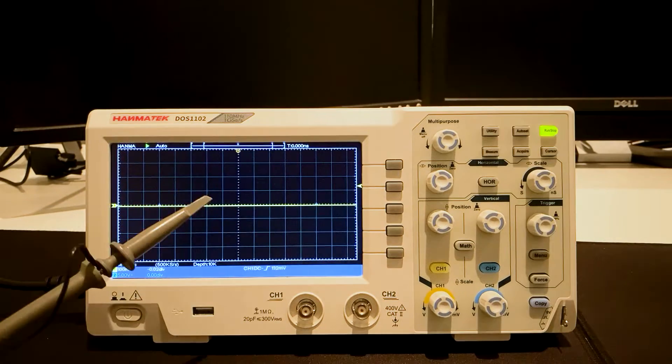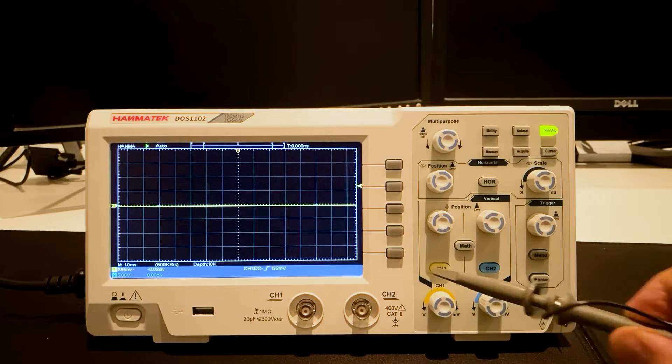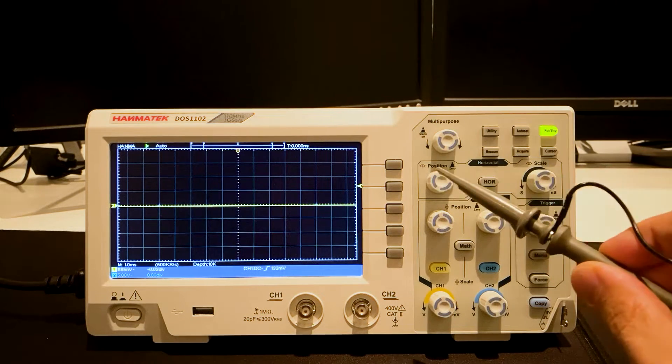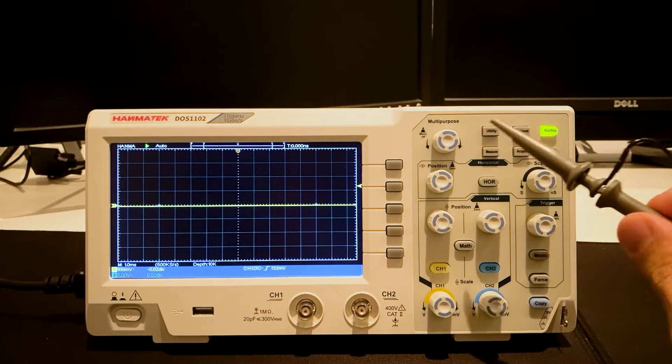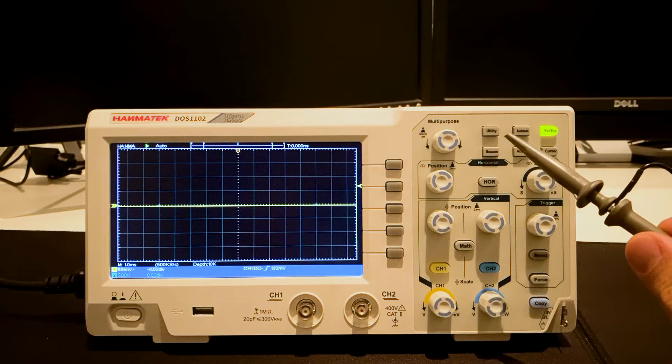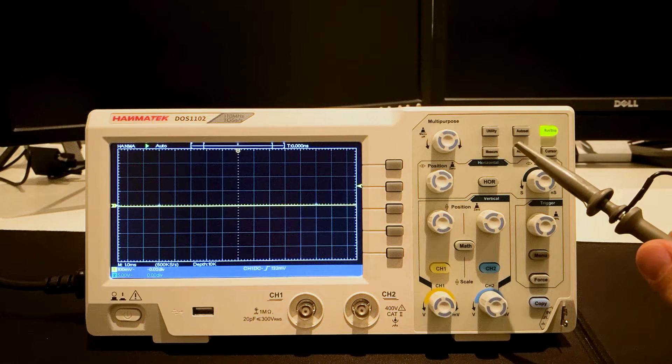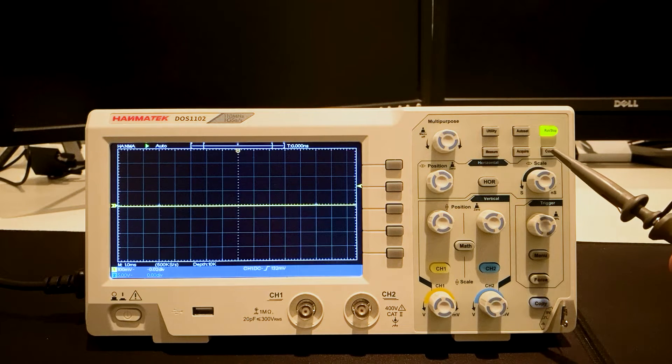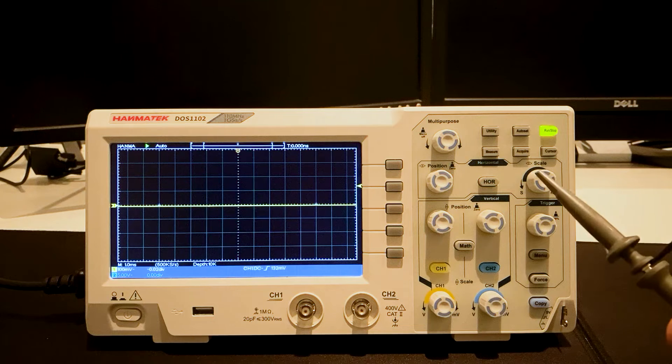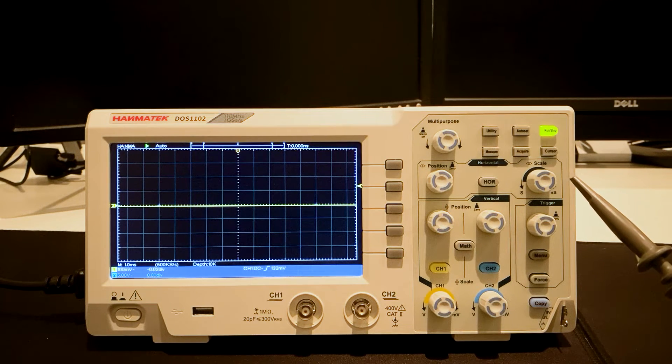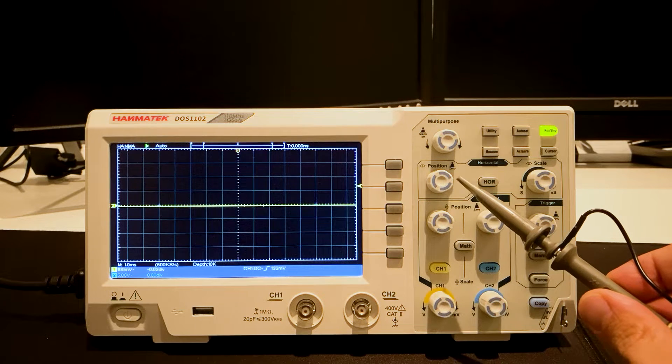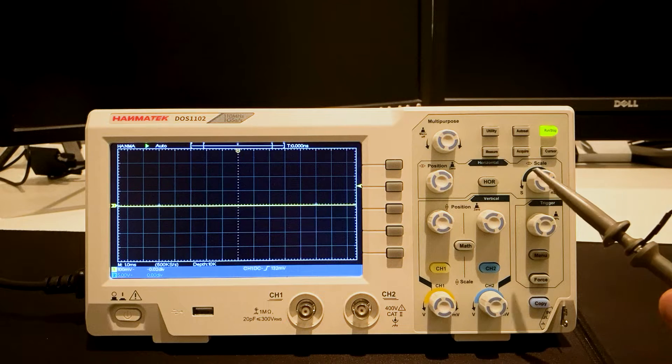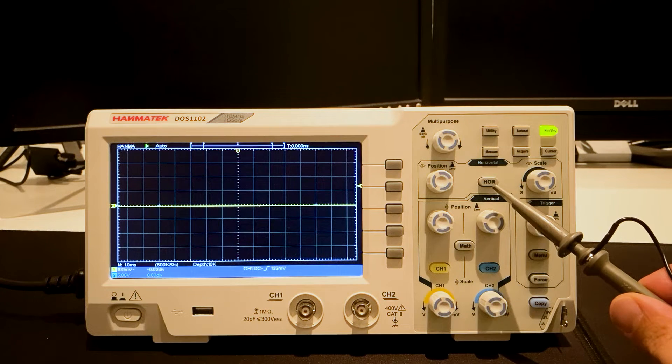The oscilloscope has a 7-inch color display. Right of the display are the menu selection buttons. On the top right side is the control area with the multipurpose knob and the buttons for the functions utility, auto set, measure, acquire, and cursor. Beneath this area is the horizontal control area containing the buttons horizontal position, horizontal scale, and the horizontal system button.